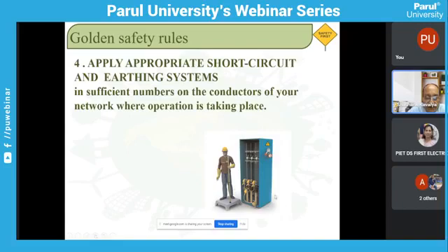After confirming that there is no power here, he does earthing of this phase, earthing of this phase, earthing of this phase, three separate discharge rods or discharge systems connected to the common earthing point. This is the common earthing point. Now it is safe to work. Even if the power comes into the system, since the earthing is there, it will trip, so persons working on the line will not get a shock.